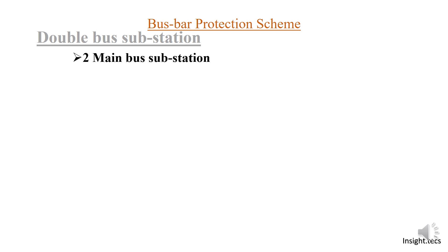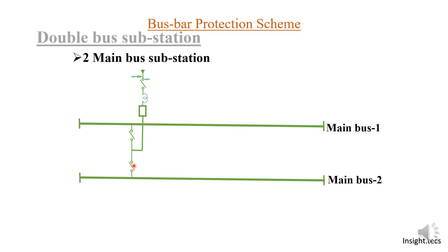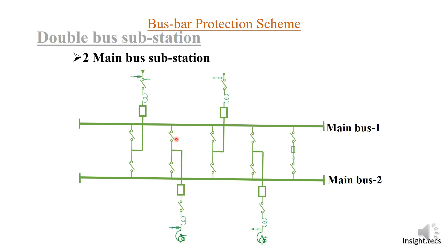Now for the double bus substation, we are discussing two main buses — bus one and bus two. The arrangement is different: for each feeder bay, there will be more isolators. You will see a selection isolator provided to select bus one or bus two. Similarly for a transformer bay, it will have two isolators for selecting bus one or bus two. There are many combinations that can be done using these isolators — they can select either bus, be connected to both buses, or use a bus coupler.